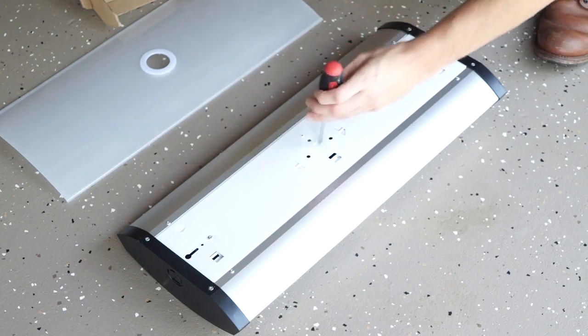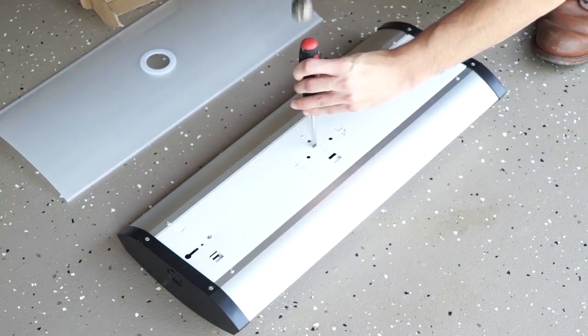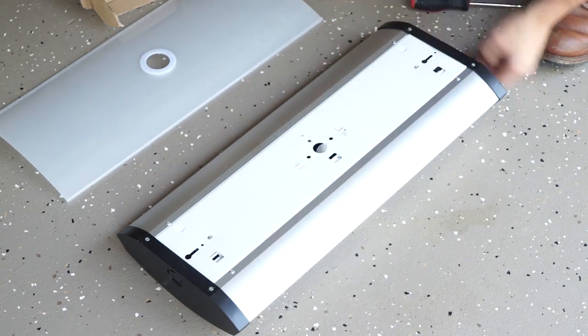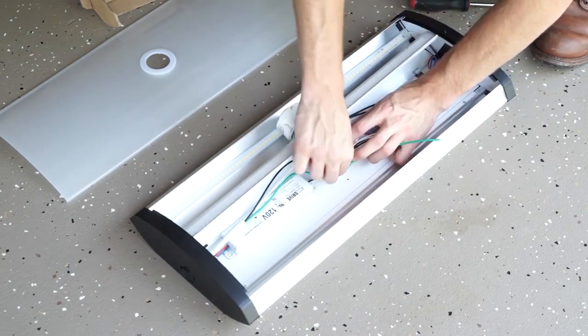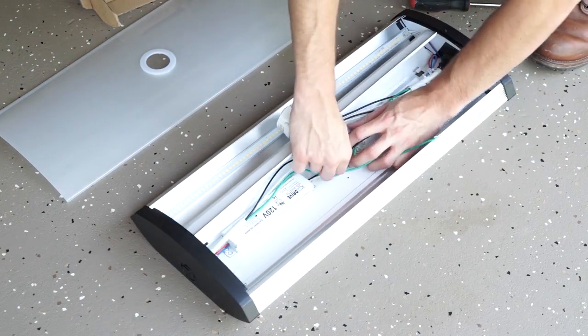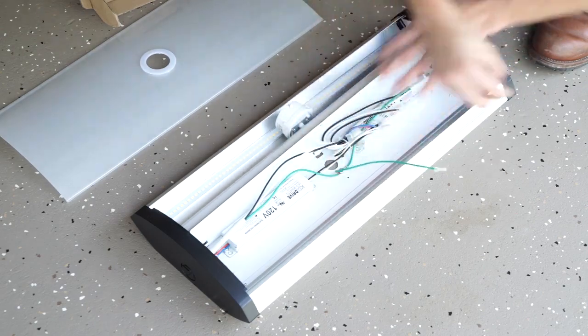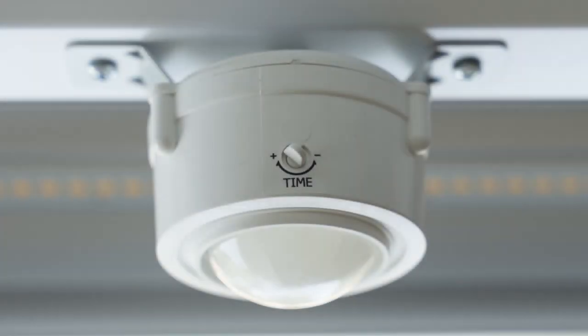On the back of the fixture, remove the 7/8" knockout at the center of the fixture by placing a straight blade screwdriver on the knockout and striking the screwdriver sharply with a hammer. Remove the slug by flexing back and forth until it comes off. Please be sure not to lay the fixture directly on the PIR sensor as it is fragile and can break.